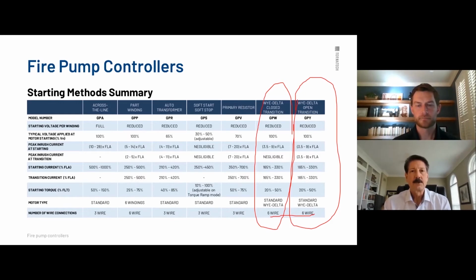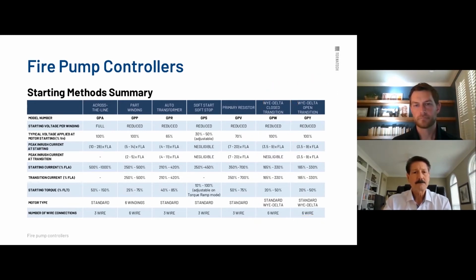And again, you're looking at a trade-off between a Y delta open or closed controller compared to a soft start. Even for reduced voltage, I would really push a soft start because it has a lot more flexibility and there's less potential, how do I want to put it, moving parts that could wear out down the road. The big thing here, as you'll note, 3-wire, 3-wire, 3-wire, 6 and 6.